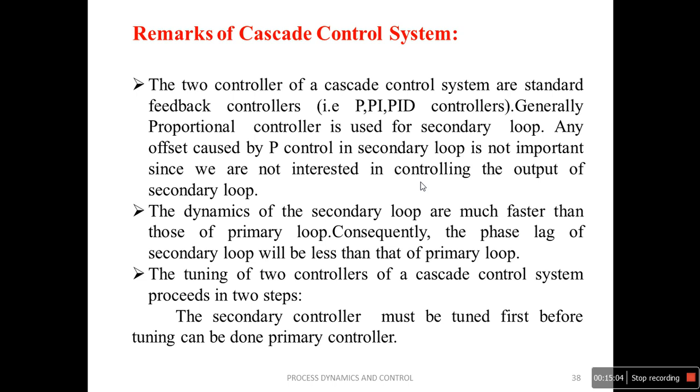So in order to have effective control, the phase lag or delay of the secondary loop must be less than the primary loop.